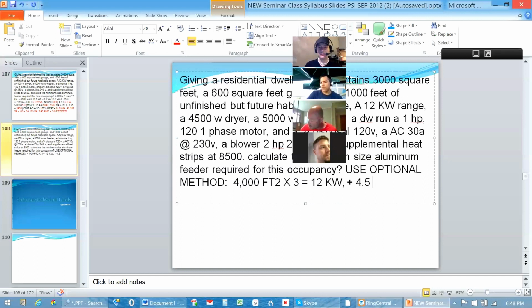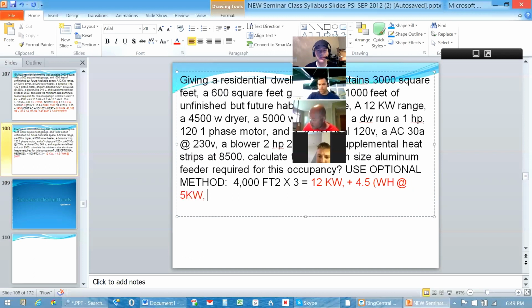So I've got a value here that I'm not going to do anything with right now. I'm going to go under B3, and B3 has a list of a whole bunch of stuff: A, B, C, and D. They're basically all the other things that we did in the standard method. A is all appliances fastened in place, which, if you remember, we could take a 75% derating on in the standard method. We had 4 or more. Here it's the nameplate of everything in the house, basically. So the water heater was the fastened-in-place appliance that we had, which doesn't include your range, dryers, motor loads, things of that nature. The water heater at 5,000 watts was the only one we had there. I'm just going to take the whole amount at 5 kW. And that's pretty much it for the fastened-in-place appliances that aren't motor loads and that aren't air conditioning or ranges or dryers.